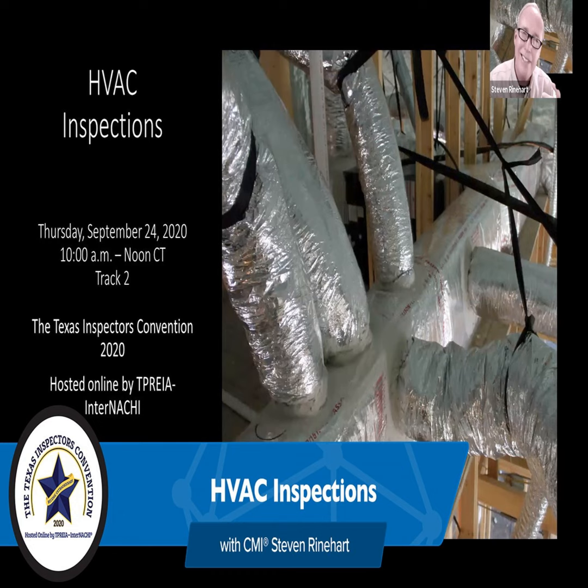There's been times where maybe 10 degrees, 12 degrees is probably as good as this thing's going to get because it's raining, it's 100% humidity, and you can almost see frost coming out of the grills. It's so humid. Not frost, but moisture. But anyway, you got to look at that.